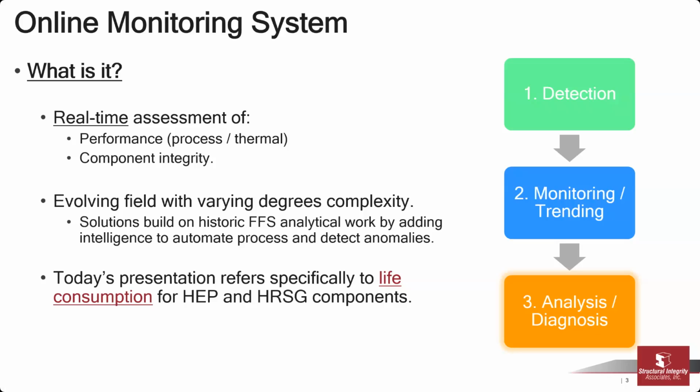So we send the data over to Structural Integrity, and they have their Plant Track software that they use to collect the data and analyze the data, and then it gives us some good results for things like creep life and fatigue life. It looks for high temperature differentials, and can give us alerts when something is abnormal or there's a component that's accruing more than normal damage. So that's an overview of what we're looking for and what we're trying to accomplish. Next slide.